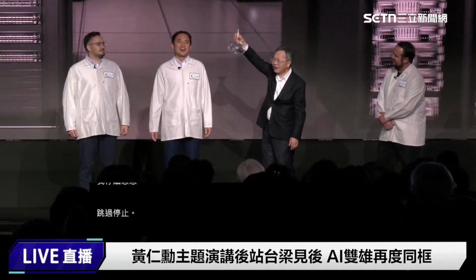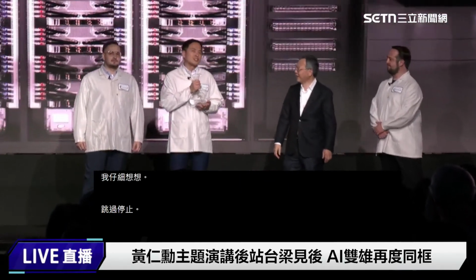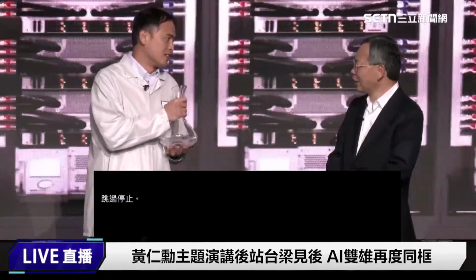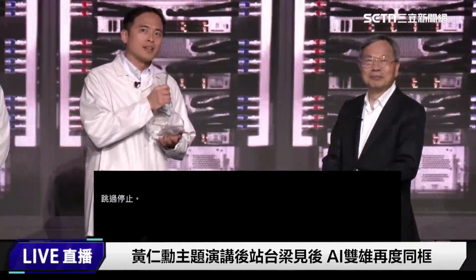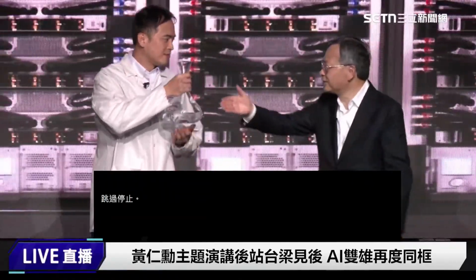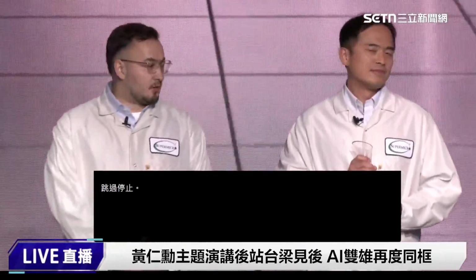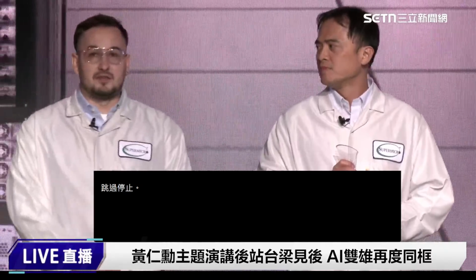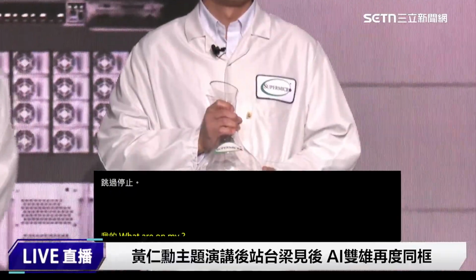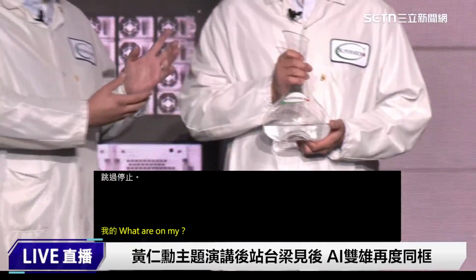This is our latest and greatest coolant innovation, just from our lab. Our team of scientists has been developing this PG DLC2 coolant for the past year. And we are bringing the best out of our DLC solution with this new coolant solution. What's the difference? Traditional PG25 works, but we have developed for the past year this optimized formulation with ultra-high electrical impedance. So we are so proud today to announce this new Supermicro PG DLC2.